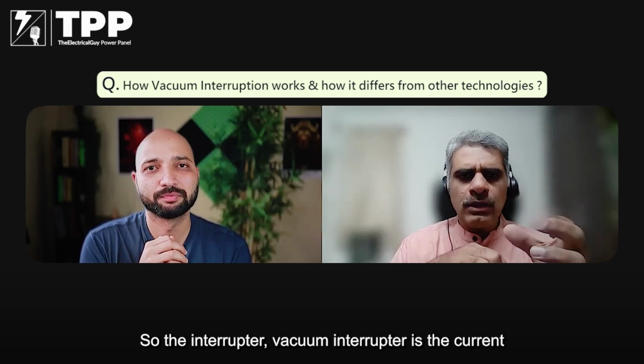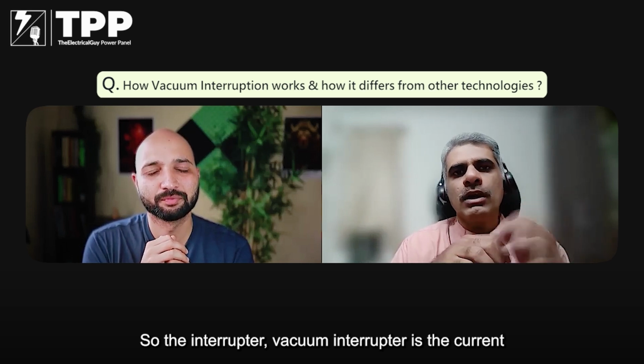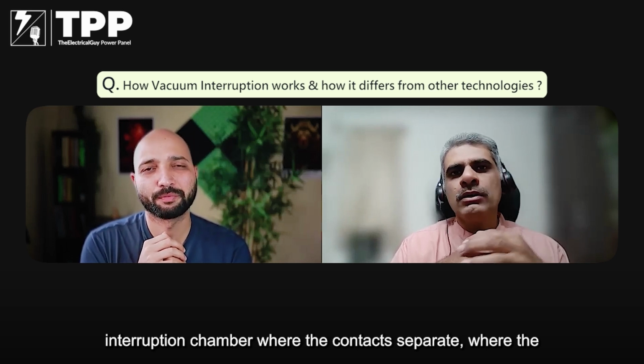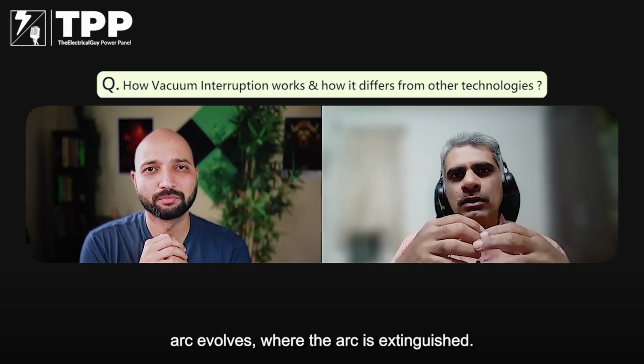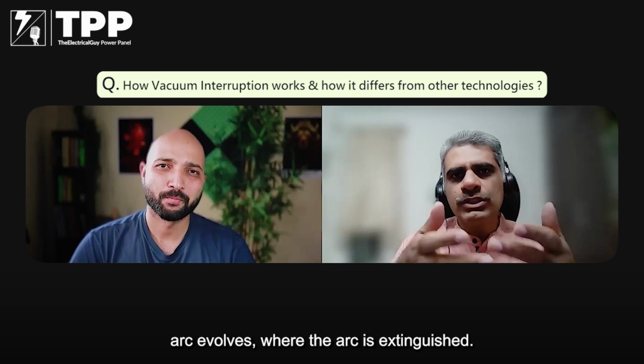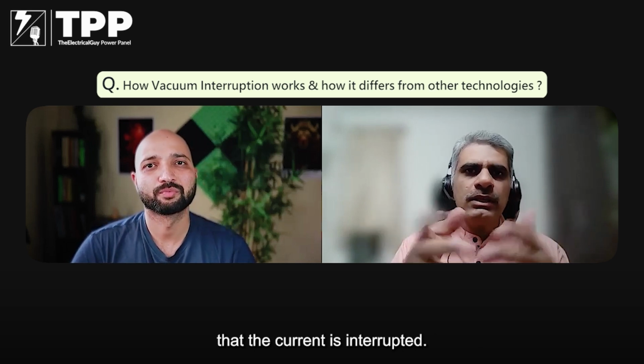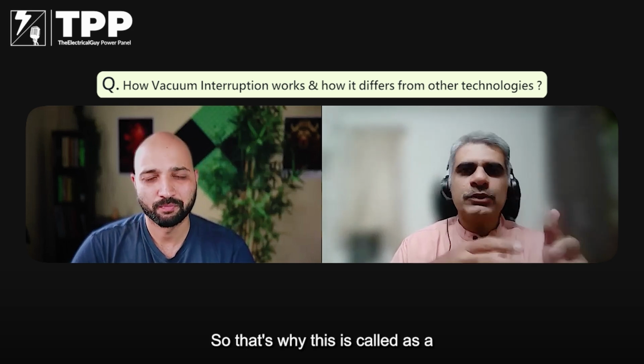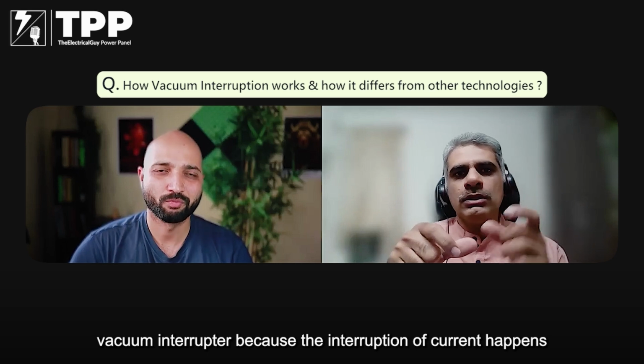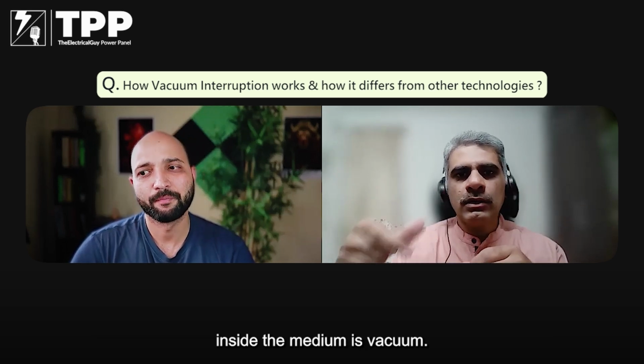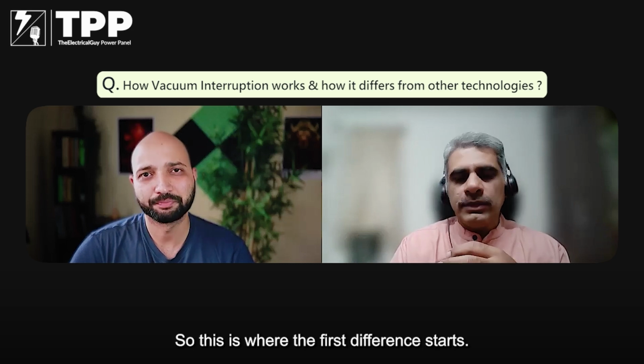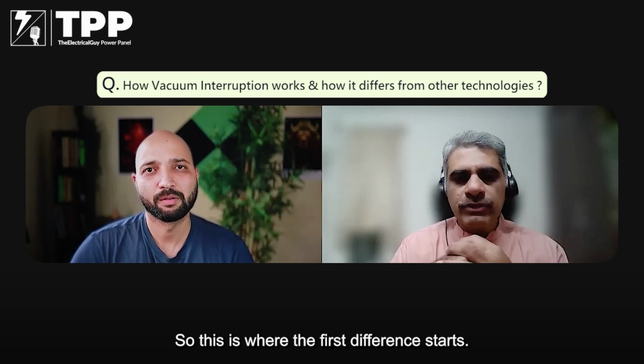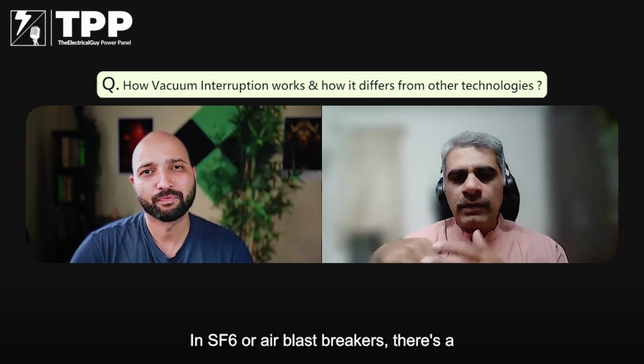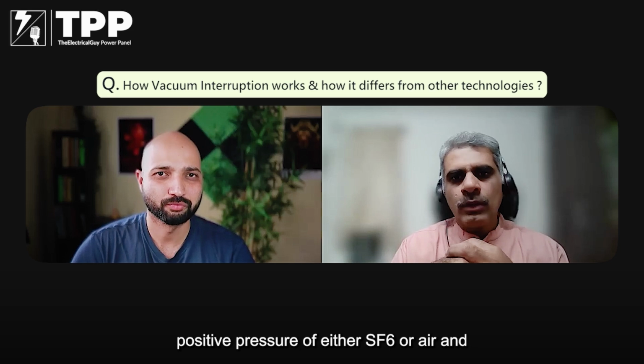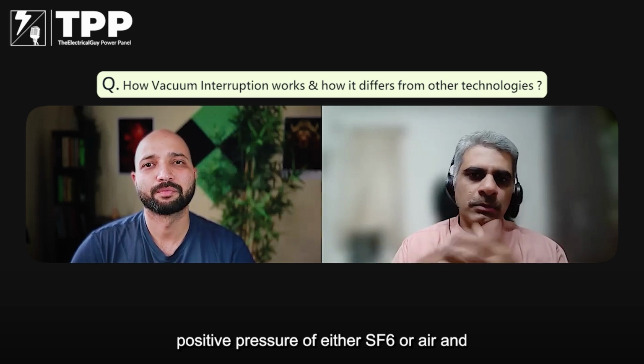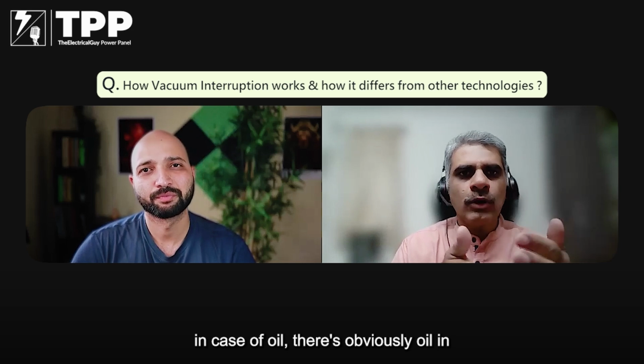The vacuum interrupter is the current interruption chamber where the contacts separate, where the arc evolves, and where the arc is extinguished, and as the arc is extinguished, we say that the current is interrupted. That's why it is called a vacuum interrupter, because the interruption of current happens inside a medium that is vacuum. So this is where the first difference starts. In SF6 or air blast breakers, there's a positive pressure of either SF6 or air, and in the case of oil, there's obviously oil in liquid form.